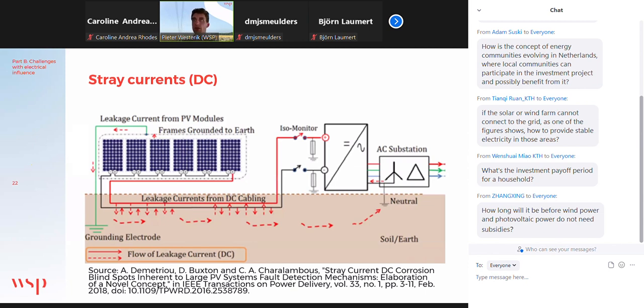And then there is another effect that is, well, I wouldn't say specific for PV plants, because for a long time we have had DC trains close to pipelines, and it is already known that these DC currents can run through the ground and cause increased corrosion on the pipelines. But recently, pipeline owners have become more concerned that PV plants, which also have a lot of DC currents, will also cause these problems. And this was actually very interesting for me.